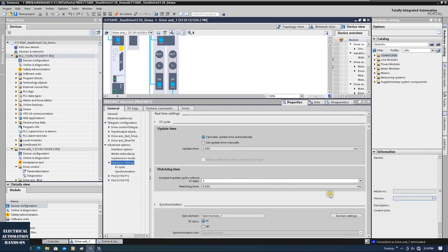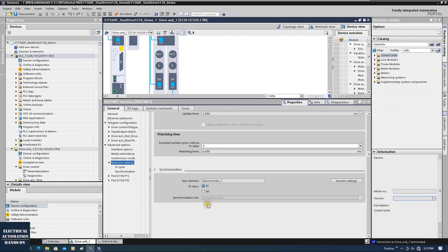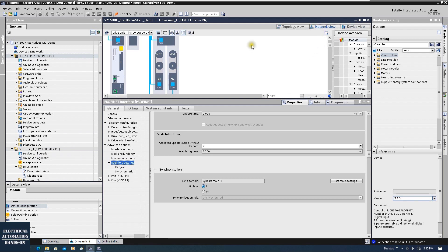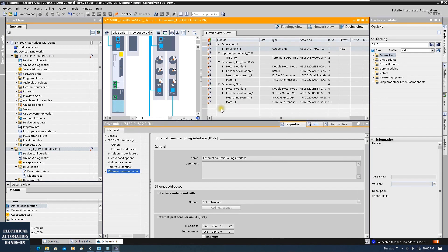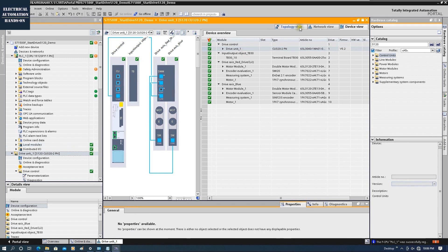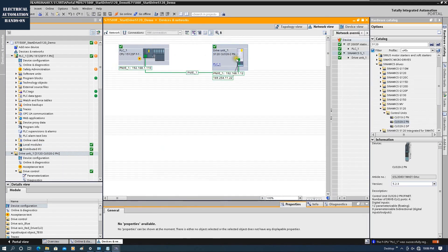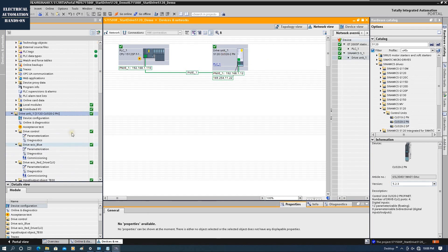This device name is the key connection between the PROFINET controller and the PROFINET device — in this case, the PLC and the Sinamics S120 servo drive. The device name is 'Drive_unit_1'. Currently we are using RT communication — standard RT communication — and we only set up the hardware configuration first. In the next video, I will set up IRT communication and the TO technology object. PROFINET RT connection covers most cases, but for servo drive motion control we need IRT. After assigning the PROFINET device name, let's go online to verify — and as we can see, everywhere shows green. The PROFINET communication is set up successfully.